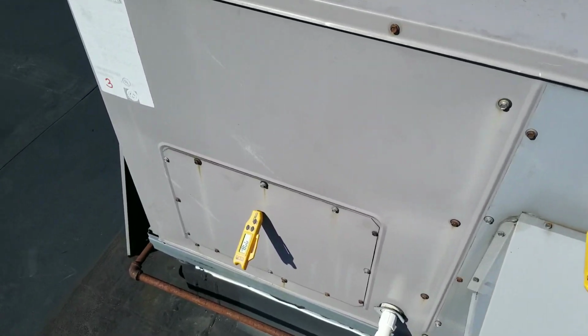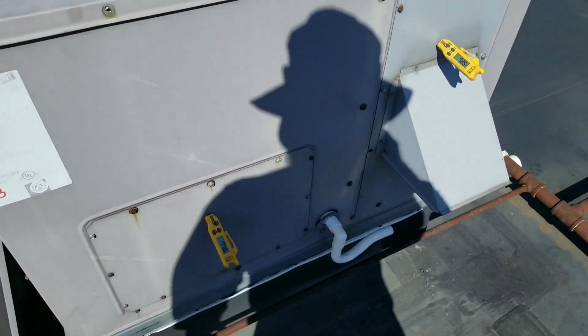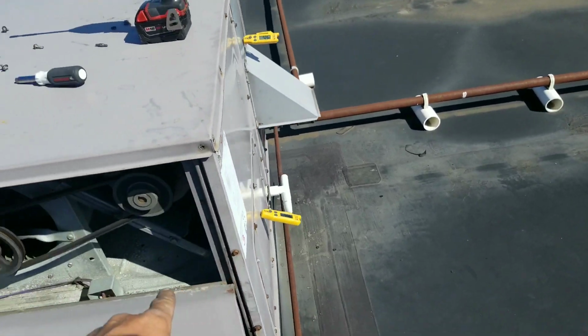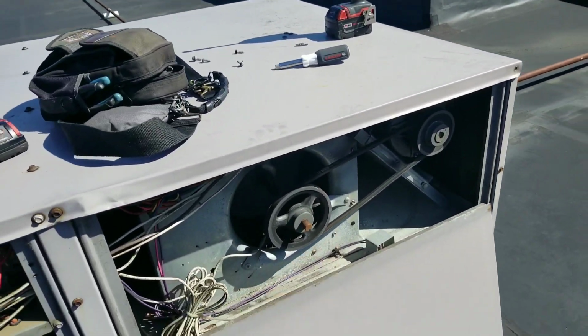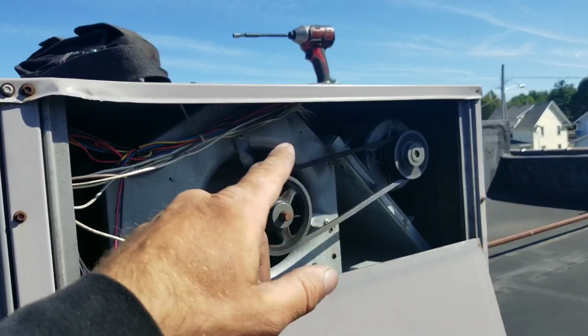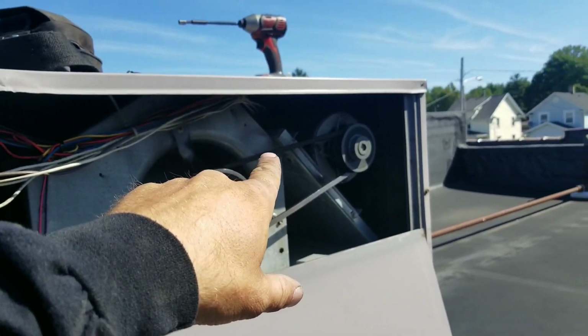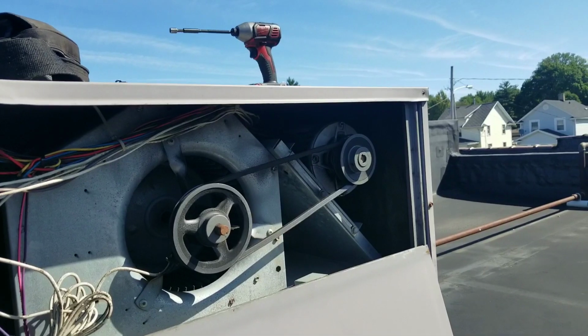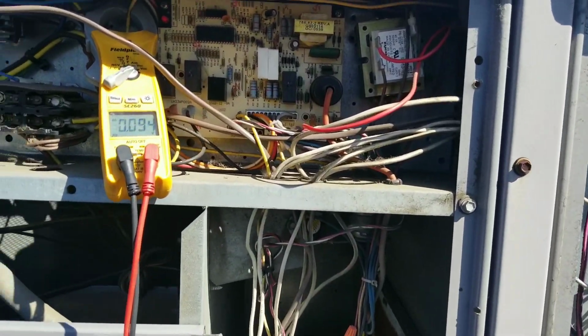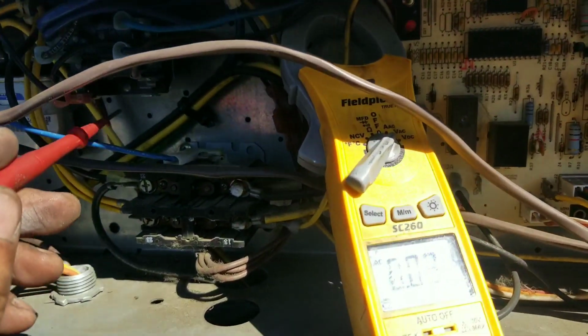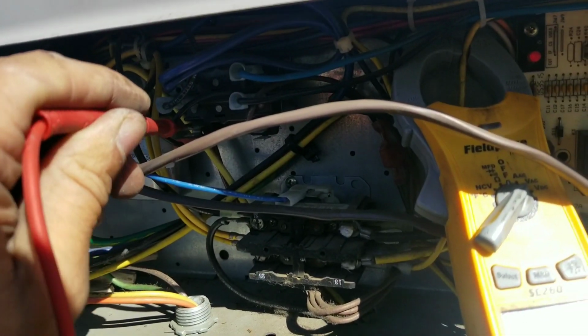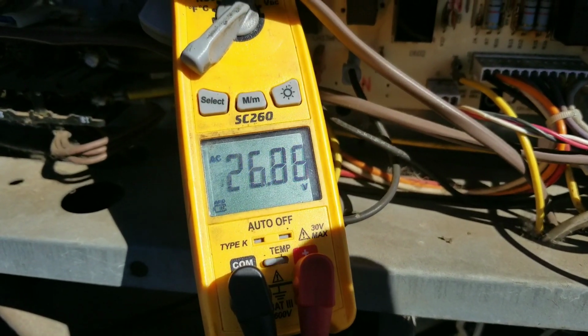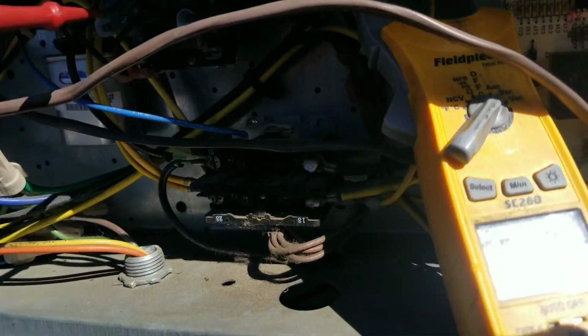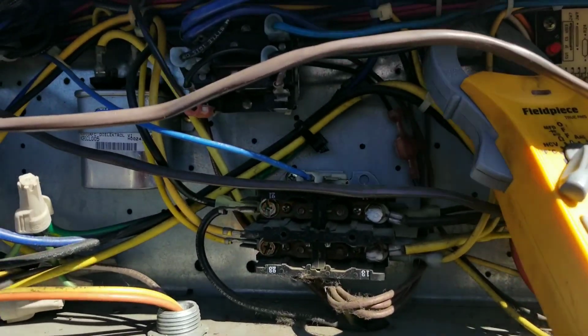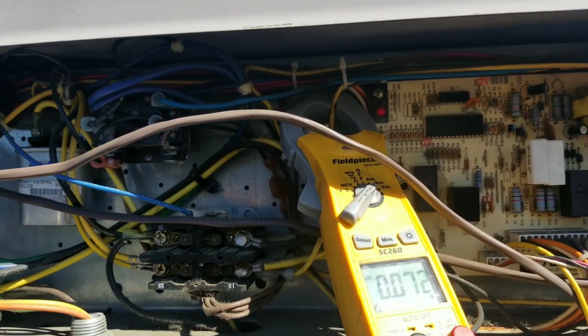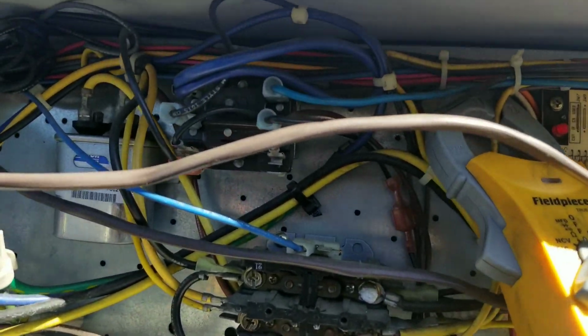Well, I let her run for about 5 minutes. And my supply temp never really dropped. So I pulled this panel off. I found my blower motor isn't turning. And really quick, I double checked all my wiring inside that blower motor just to make sure that I didn't forget to put something back together. And that's all fine. So let's come over here to our relay just to see if we're getting voltage on our blower relay. We do have voltage on our relay, so our relay should be closed. Now we just need to check and verify that we actually have power going to our blower motor.